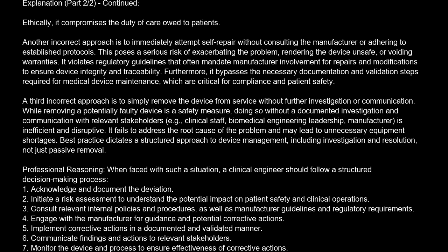Professional reasoning. When faced with such a situation, a clinical engineer should follow a structured decision-making process. 1. Acknowledge and document the deviation. 2. Initiate a risk assessment to understand the potential impact on patient safety and clinical operations. 3. Consult relevant internal policies and procedures, as well as manufacturer guidelines and regulatory requirements. 4. Engage with the manufacturer for guidance and potential corrective actions. 5. Implement corrective actions in a documented and validated manner. 6. Communicate findings and actions to relevant stakeholders. 7. Monitor the device and process to ensure effectiveness of corrective actions.